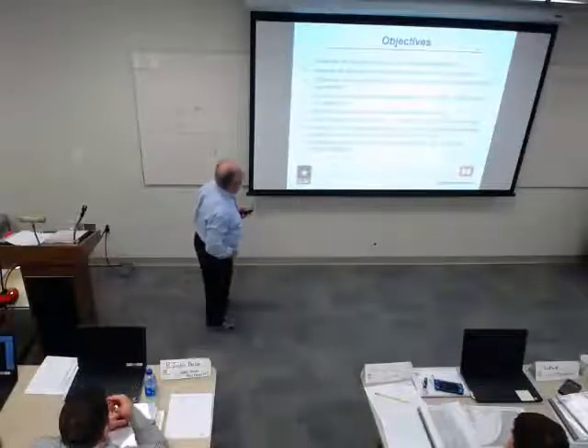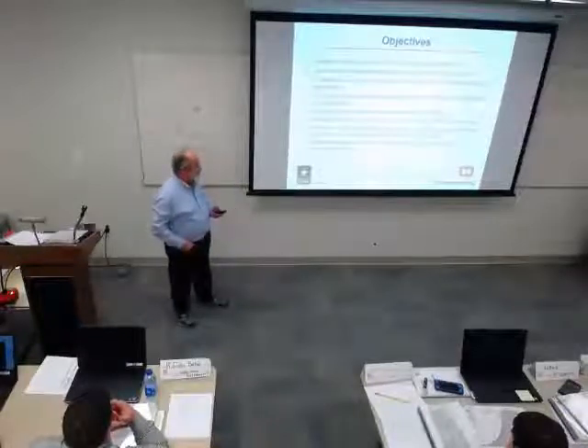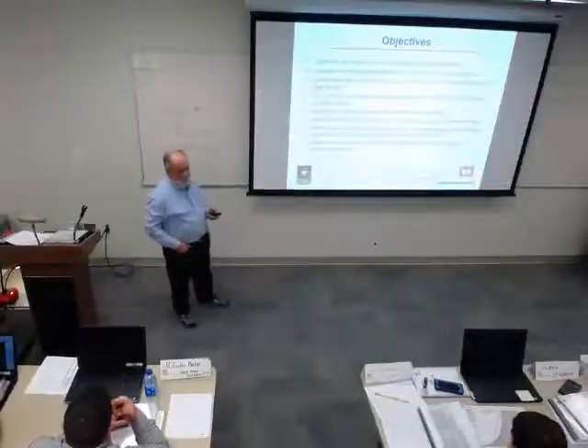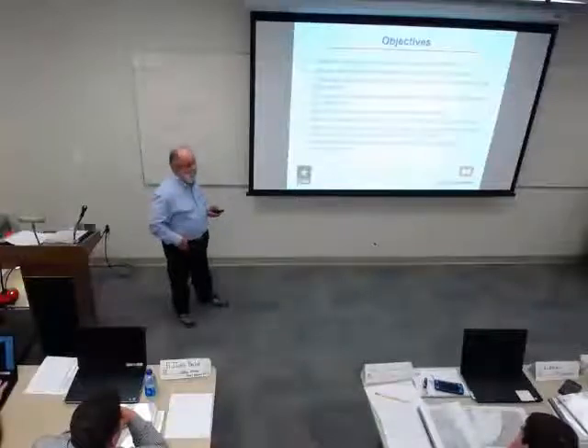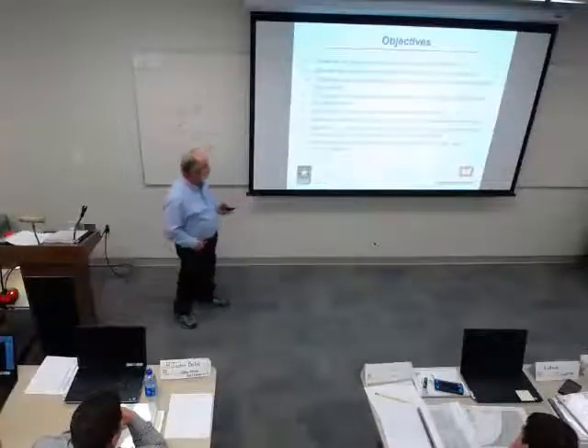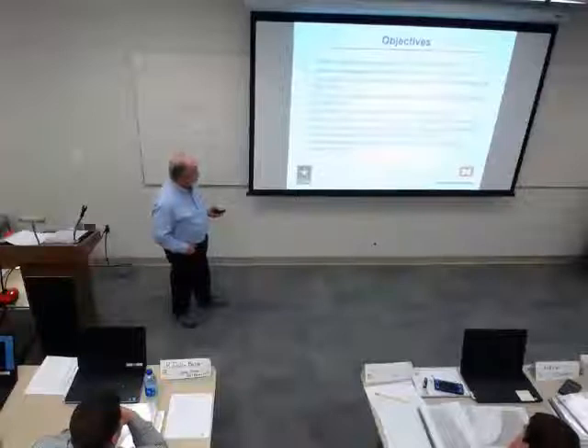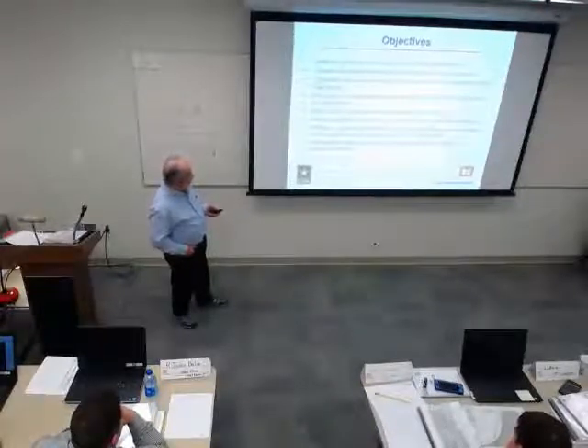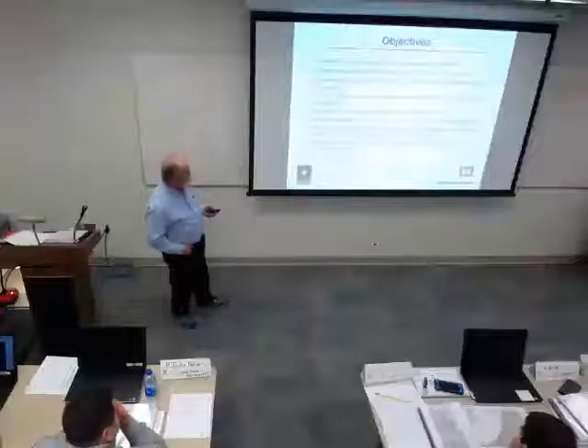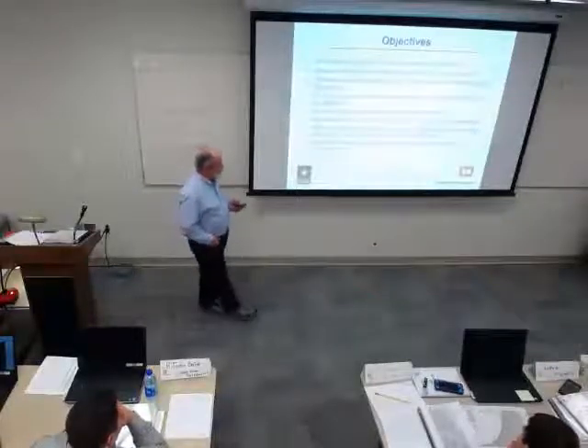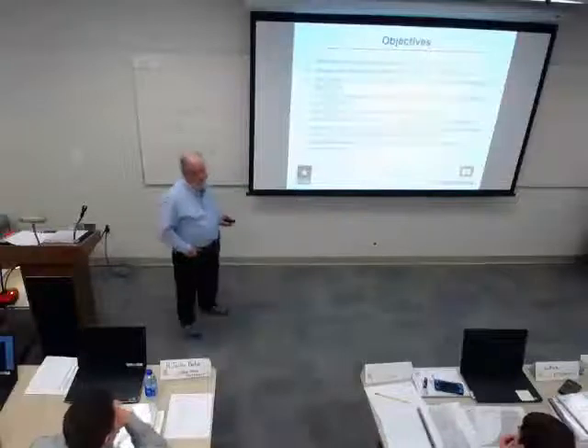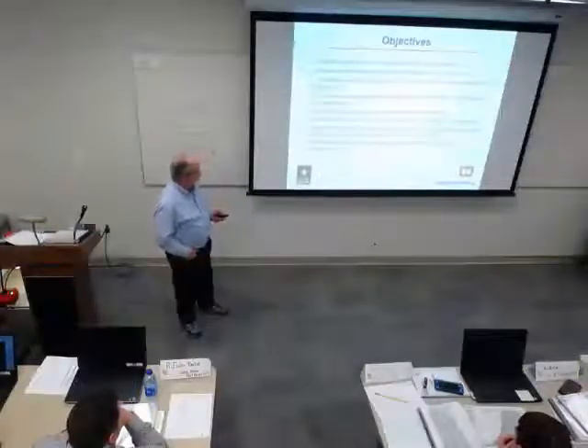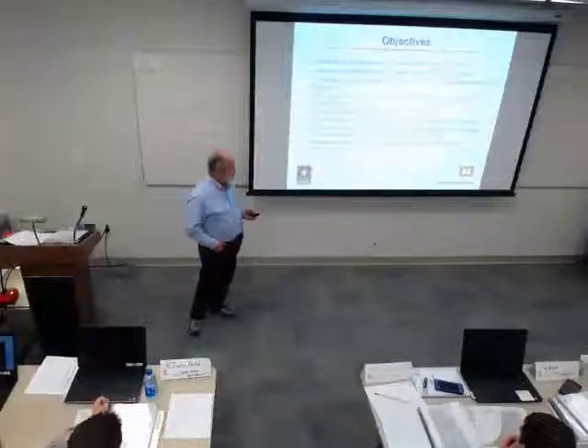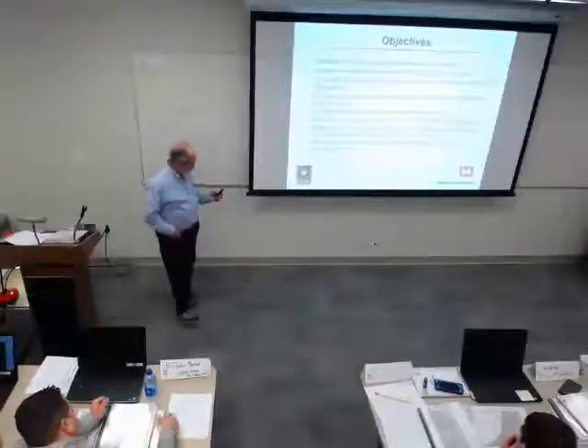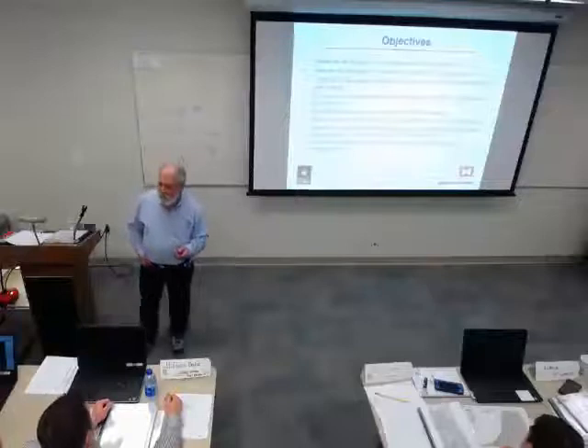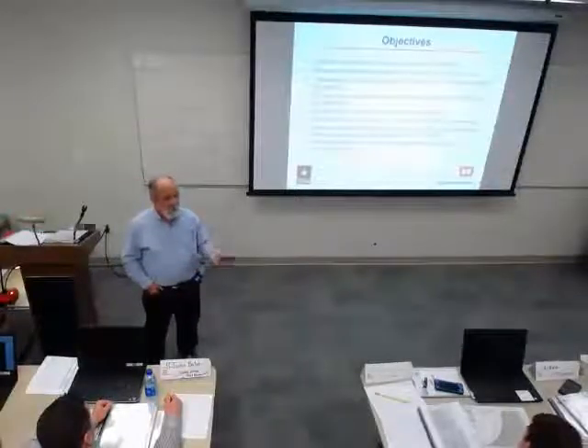We're going to describe how airflow impacts space cooling and heating, and the amount of outdoor air in a system, using mixed air temperatures to find out the mix, what percentage of outside air there is. Using the psychrometric chart, we determine temperature, humidity, energy, and density conditions of air, given any two of those values. Then we're going to determine the flow rates at coils using the psychrometric chart and heat transfer equations. All of this, plus a little bit, you're going to get into in the labs.